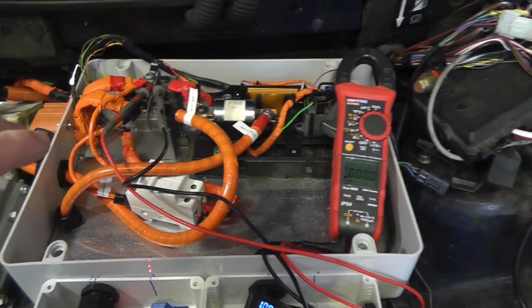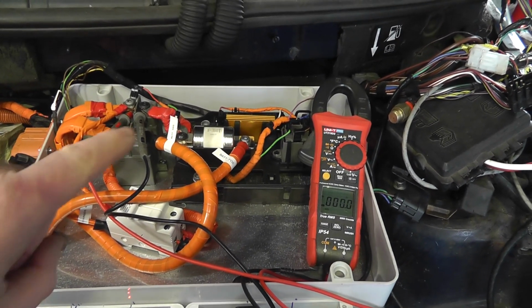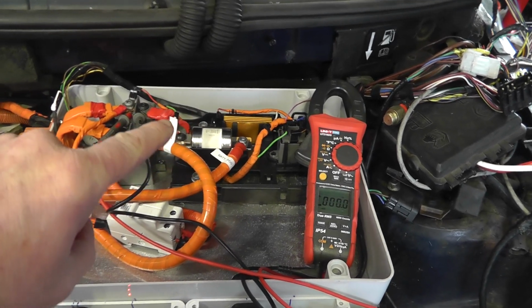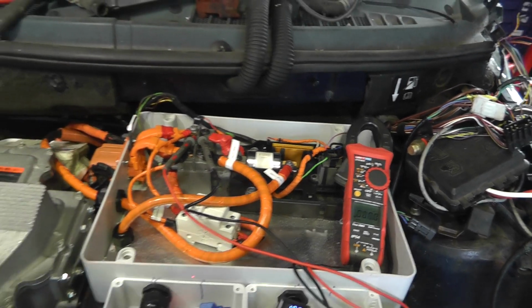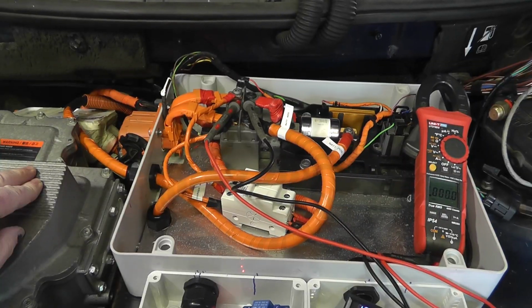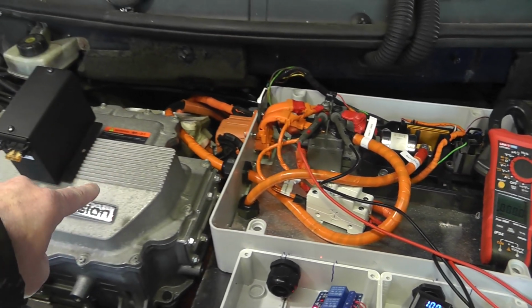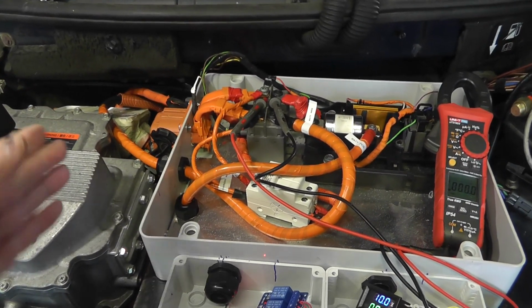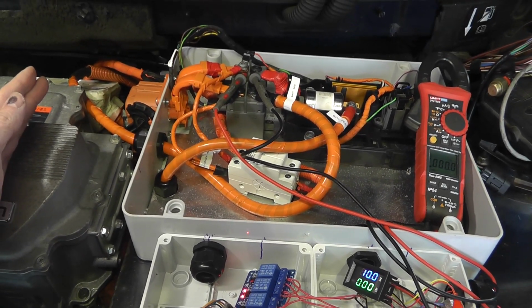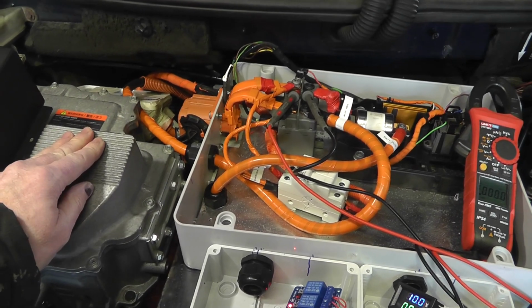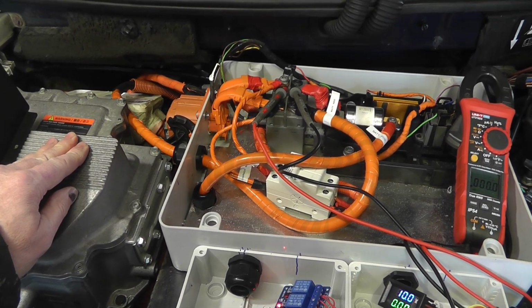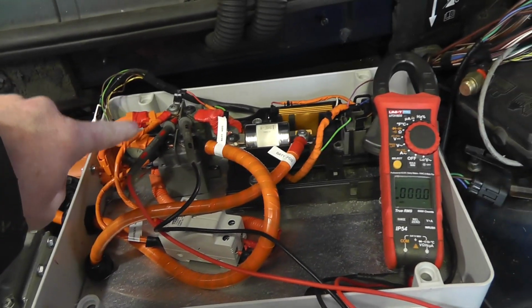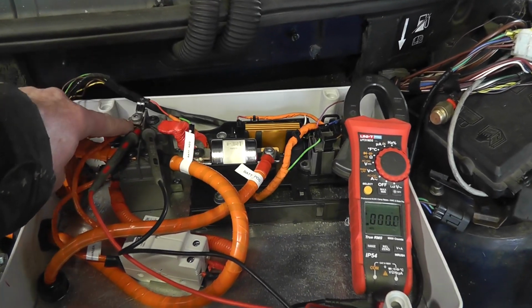So the point of all this is so that the resistor comes in first to put the 300 volts into the inverter. The reason for that is there are large capacitors in the inverter, and if you were to just put 300 or 400 volts through a switch directly into the inverter, there would be a massive inrush of current, enough to destroy the contactors.